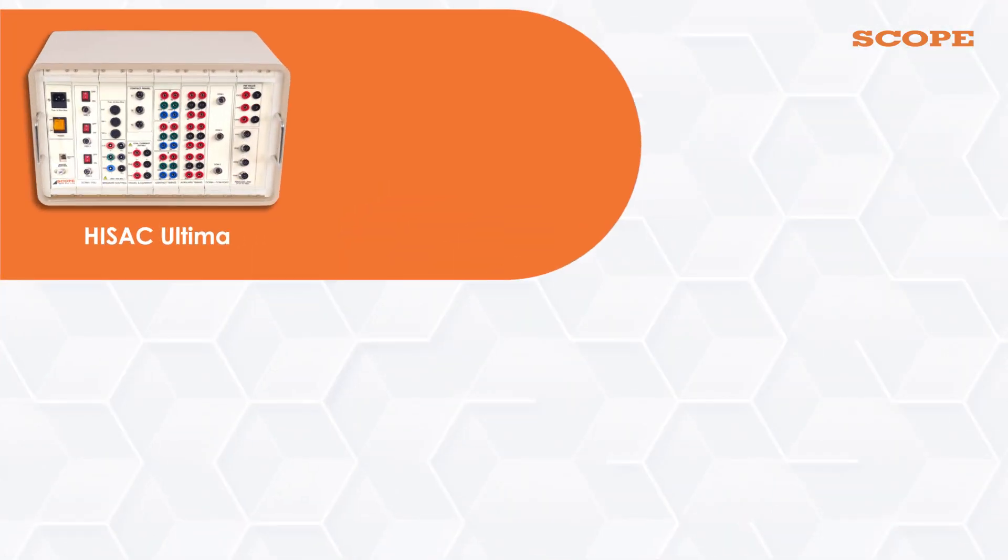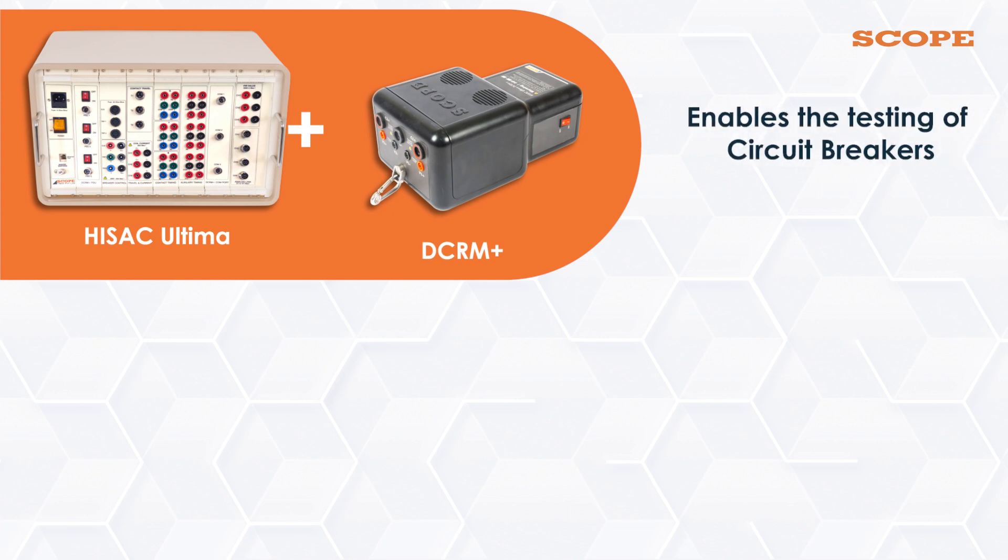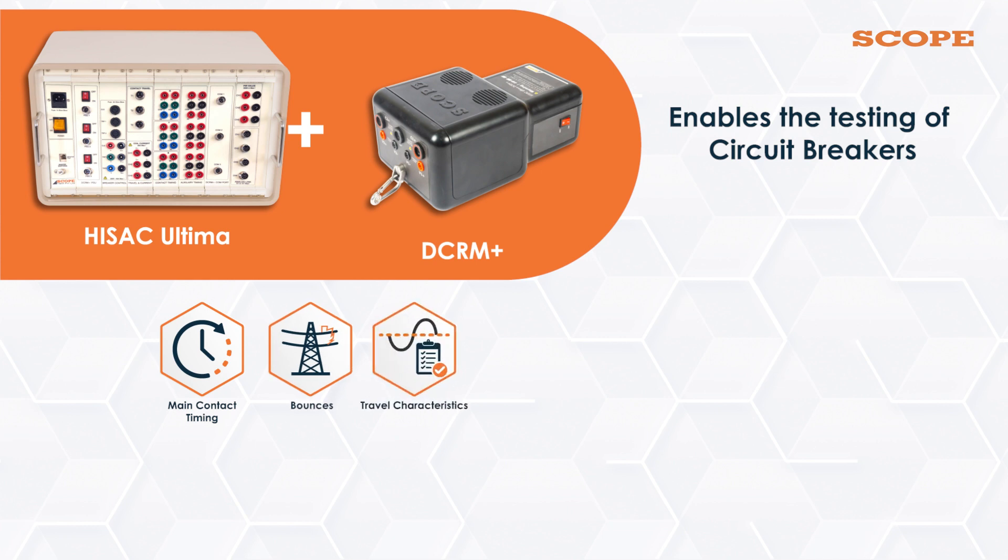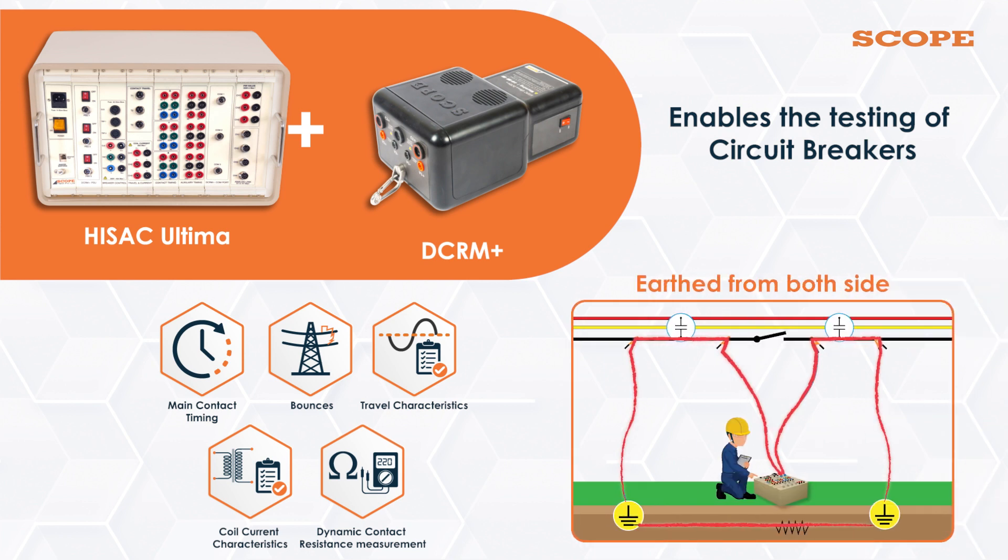HISAC Ultima, coupled with DCRM Plus, enables the testing of circuit breakers for main contact timing, bounces, travel characteristics, coil current characteristics, and dynamic contact resistance measurement while the circuit breaker is earthed from both sides.